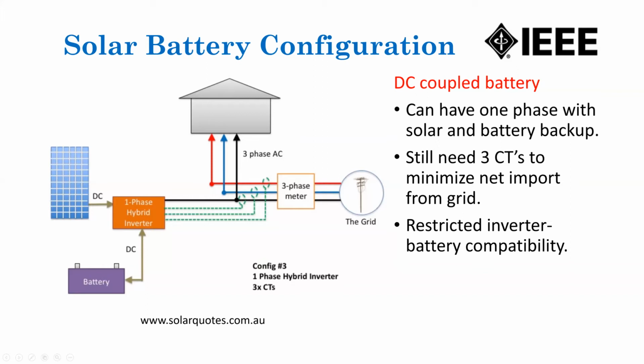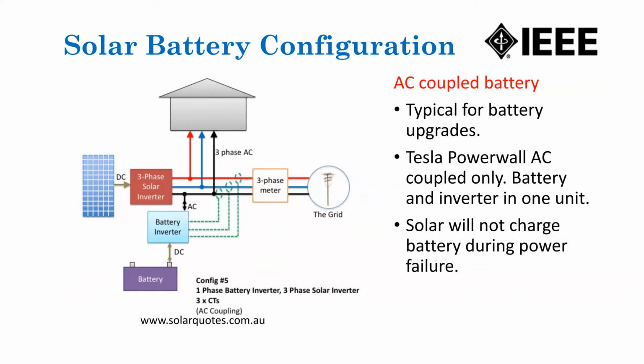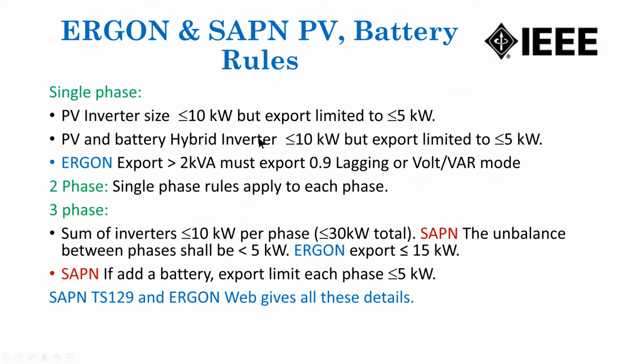So that's a DC coupled battery. You can also have an AC coupled battery. The Tesla Powerwall, for instance, is a battery with a battery inverter, and that is a single phase inverter and connects to 1 phase. And then you again have your 3 current transformers, etc. So that if the power fails, the circuit breaker operates just up here, and this phase stays on, and your solar inverter would also stop working under those conditions, because there's only single phase power available. And we'll talk about that more in a little bit.